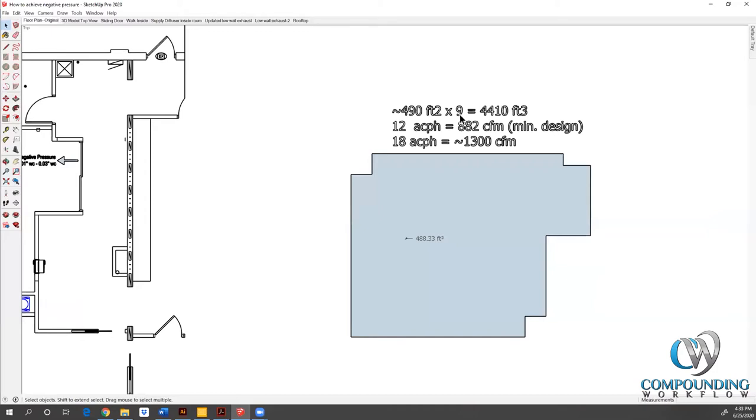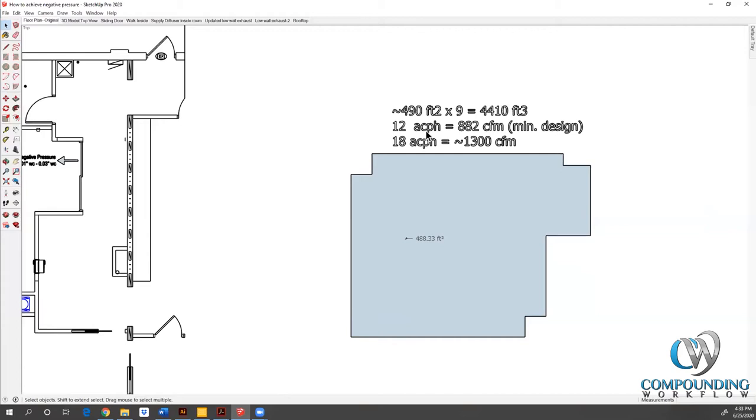The ceiling height in that room is actually nine feet. That's what the client told me. So I multiply the square footage times the ceiling height and I get the cubic footage, which is 4,410 cubic feet. USP 800 in that chapter defines for us in table one and table two, whether it's non-sterile or sterile, what our minimum number of air changes are.